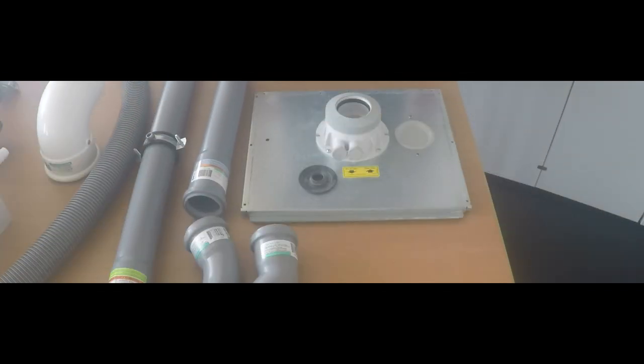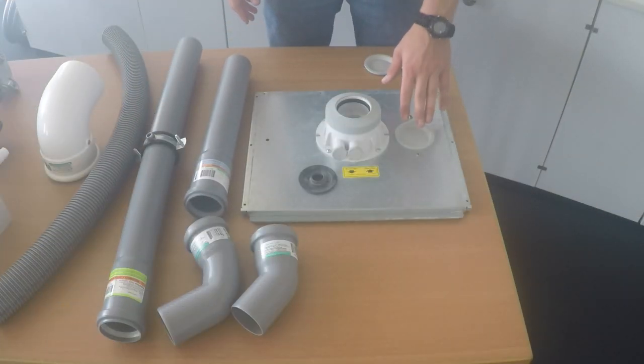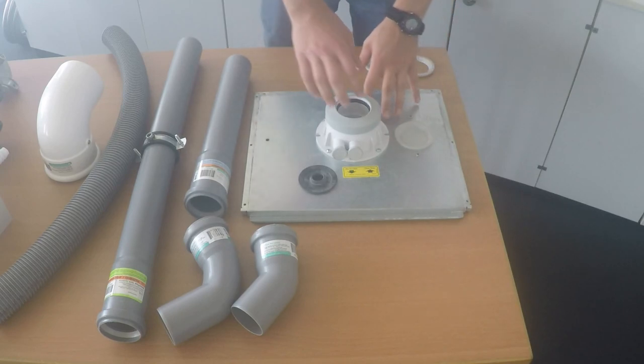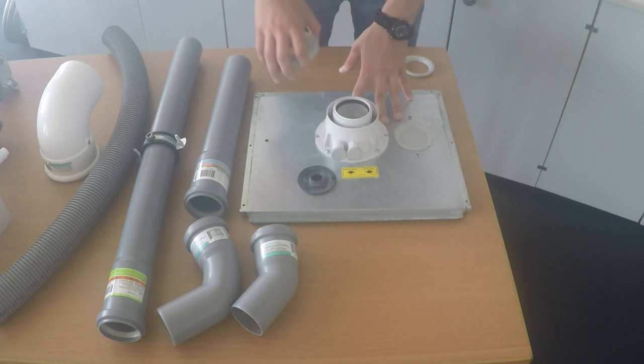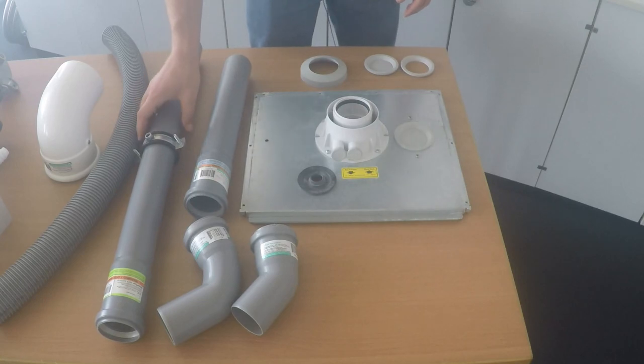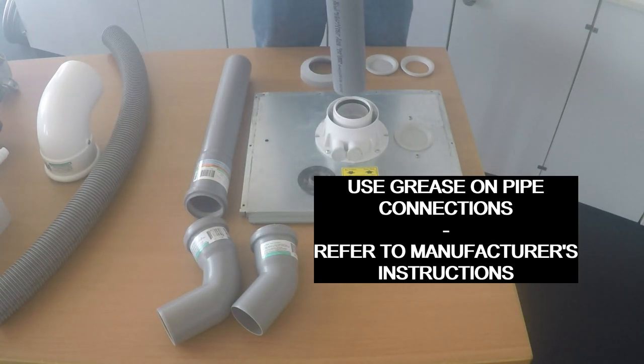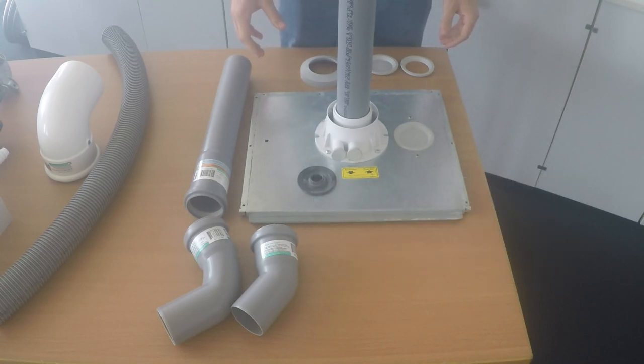The second venting method is the single pipe system. For this one, we will leave this cap alone. And instead, we will remove this cap on the center assembly. And we will take our flue gas pipe and simply put it in the middle. And this will allow the intake for the boiler to come in through this outside ring.